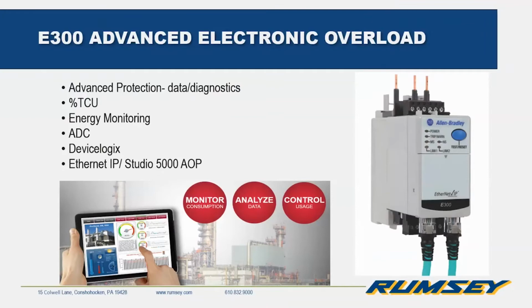Another feature is DeviceLogix. So basically this is like a mini PLC being placed in this unit, gives you some programming function in it. And this overload also has I/O, embedded I/O in it, and then you can also have additional inputs and outputs as well. So you kind of combine that with DeviceLogix, and you can get pretty creative with different applications doing some different things. And then, as you mentioned, it is on Ethernet. It's a networked overload, so that just gives you the ability to pull out all of this data, all this information, and make it useful for you. And the Studio 5000 add-on profile already has a lot of the configuration engineering done for you, just to help with the installation on it.